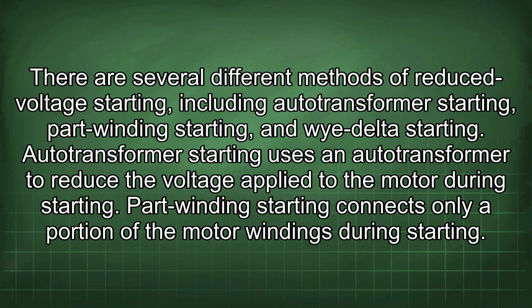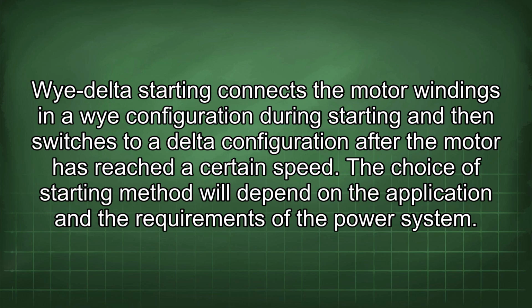There are several different methods of reduced voltage starting, including auto-transformer starting, part-winding starting, and Y-delta starting. Auto-transformer starting uses an auto-transformer to reduce the voltage applied to the motor during starting. Pot winding starting connects only a portion of the motor windings during starting. Y-delta starting connects the motor windings in a Y configuration during starting and then switches to a delta configuration after the motor has reached a certain speed. The choice of starting method will depend on the application and the requirements of the power system.